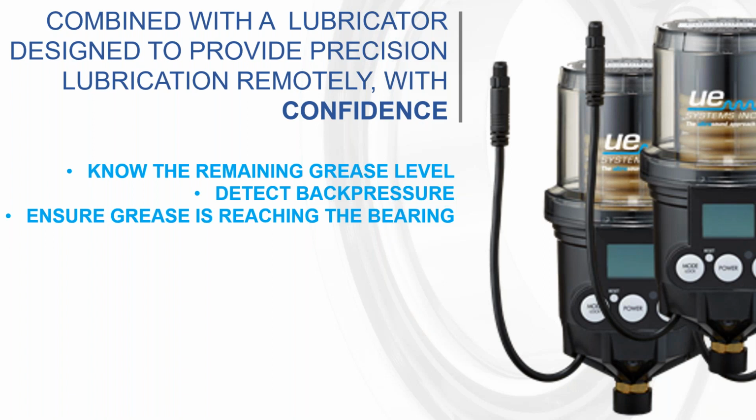So out in the field, how do we know grease is reaching the bearing? Detecting back pressure is one thing. That is, if the grease path is blocked, which can happen. But more commonly, what happens if the lubricator falls off, or the remote grease line falls off? There was maintenance and they took the single point lubricator off and forgot to put it back on. Grease lines have been cut. There are many different ways. We wouldn't be able to detect that with back pressure. So we've been able to address that specific problem with the Smart Lube logic.